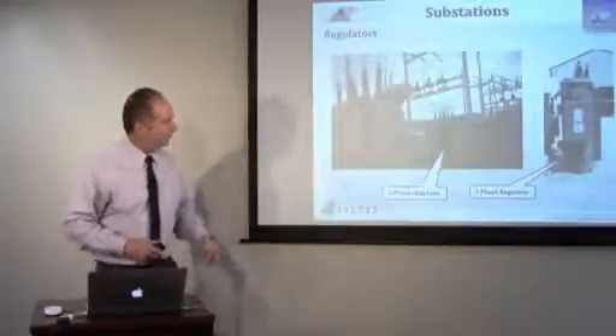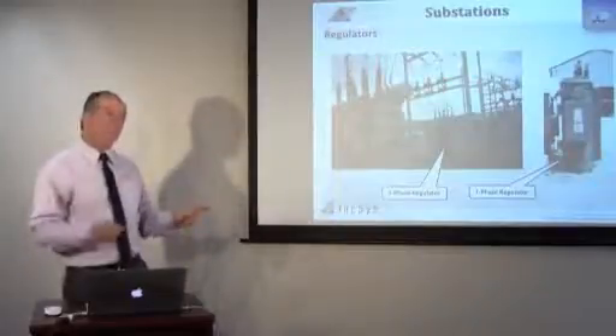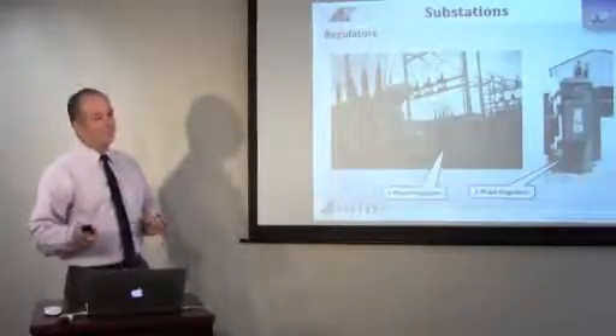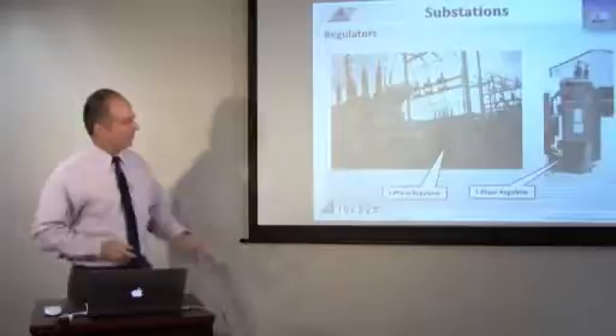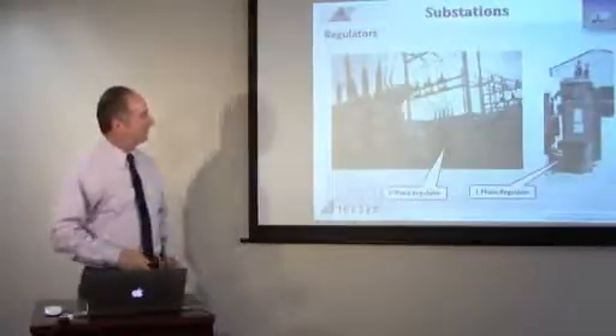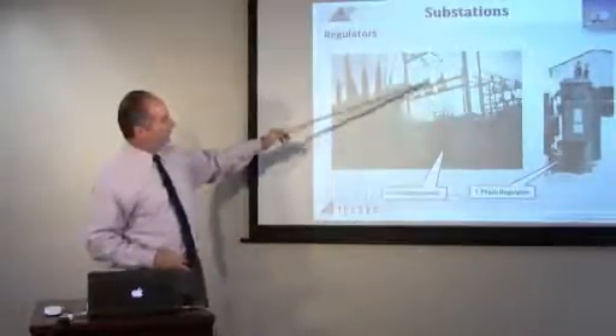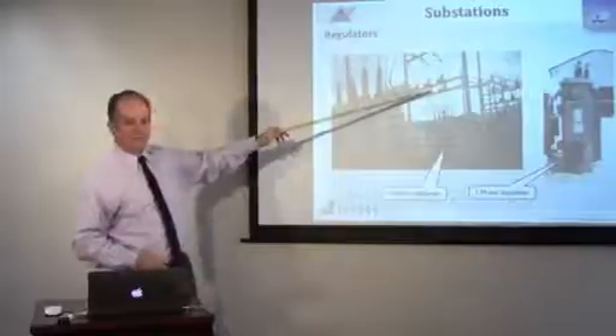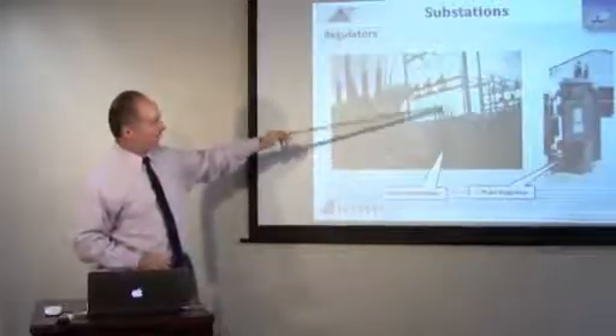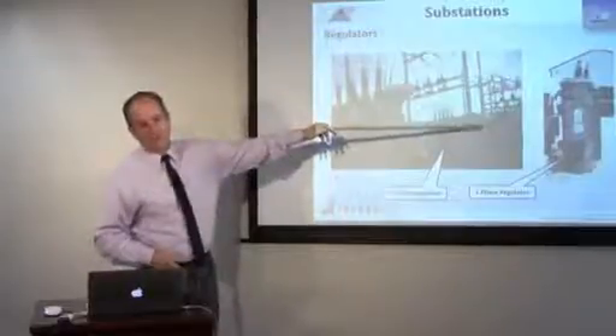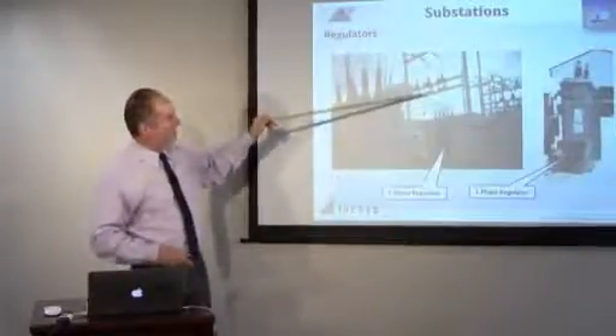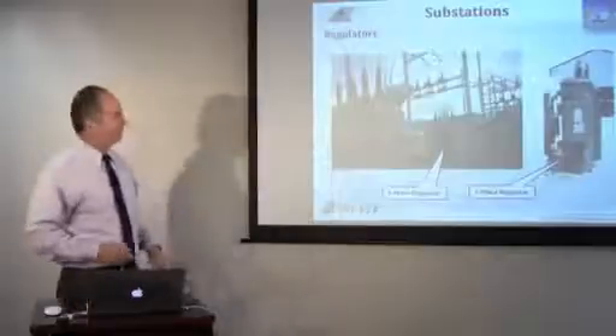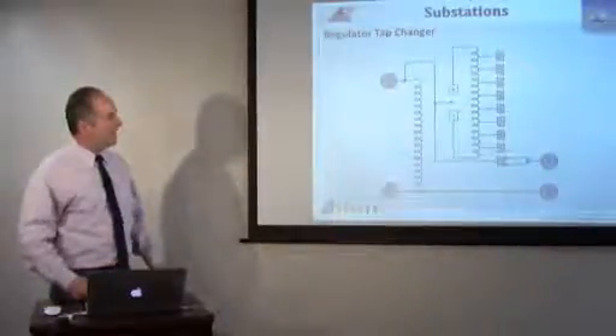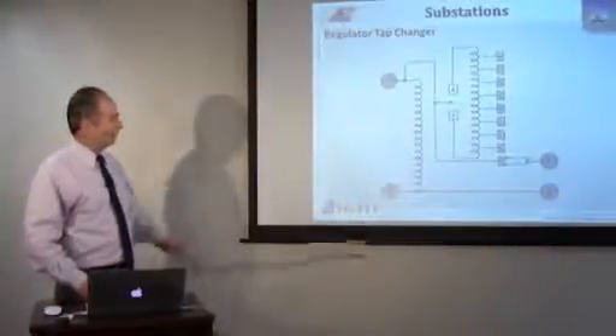3-phase regulators are cheaper than 3 single-phase ones, but a spare is more expensive and more work. So, trade-off, again, trade-off. Usually the regulators have bypass and disconnect switches for maintenance. It takes a lot of maintenance. So you would disconnect, you would bypass, so you give unregulated voltage, and then disconnect the regulator for maintenance. And here's basically how the regulator works.